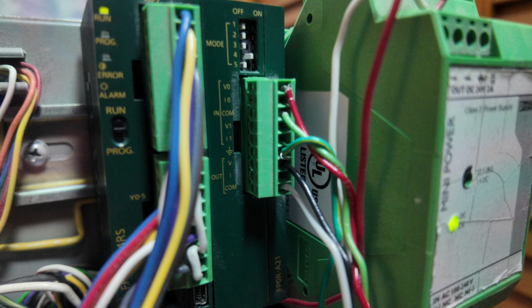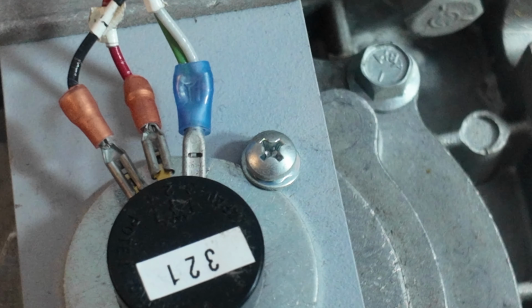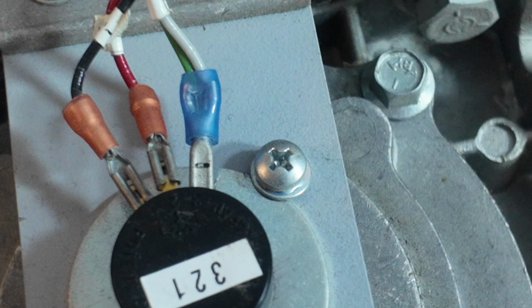The analog unit is the device that deciphers this information. It is located here, next to the PLC with the single green plug. The wires from the analog unit run in a shielded cable to the transducer. If any of these leads are disconnected or are making a poor connection, the door position can be affected and/or not read properly. Some examples of door position reading issues that can occur.